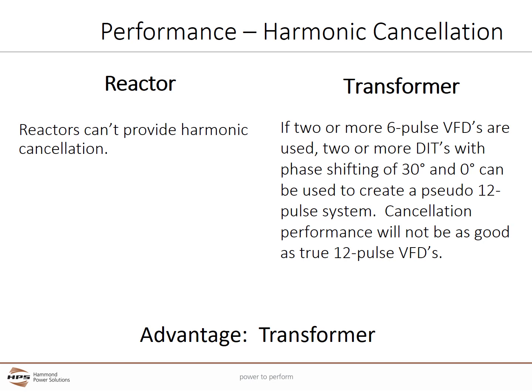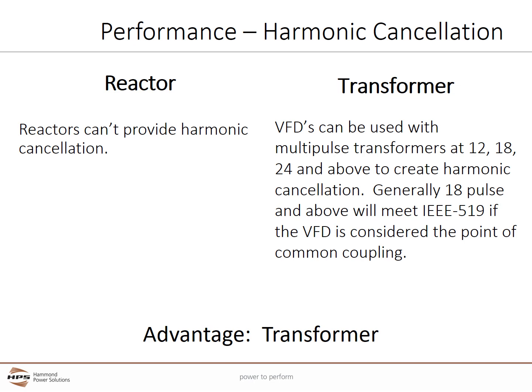Performance will be better than a standard DIT or line reactor, but it will fall below that of a true 12-pulse VFD due to varying loads and differences in cable sizes and lengths of the loads. Line reactors and transformers can both mitigate harmonics, but only transformers can perform harmonic current cancellation. Cancellation occurs when a transformer is able to phase shift some of the harmonic currents being produced in one phase to another phase such that they cancel each other out.